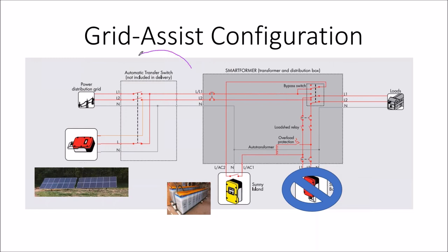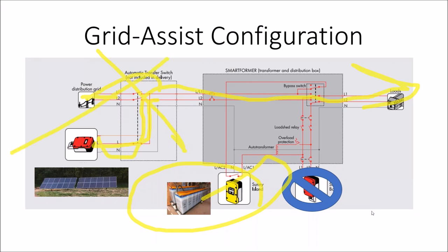You could put a transfer switch between your service, but instead of putting it between your grid connection and your backup generator, you put it between your grid connection and your solar array. So the solar array is always disconnected from the grid, never connected to it. Then you have a battery bank in between to maintain your power as you're switching. So you could run off the solar array during the day and then disconnect it at night and run off the grid at night. That's kind of neat.